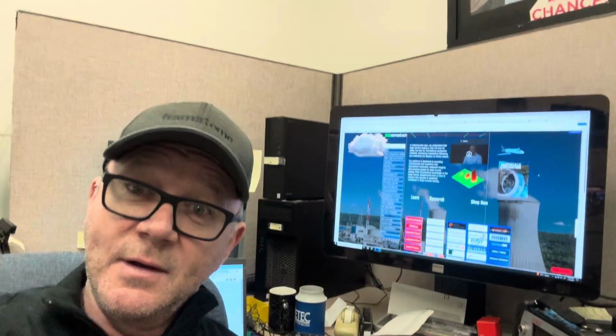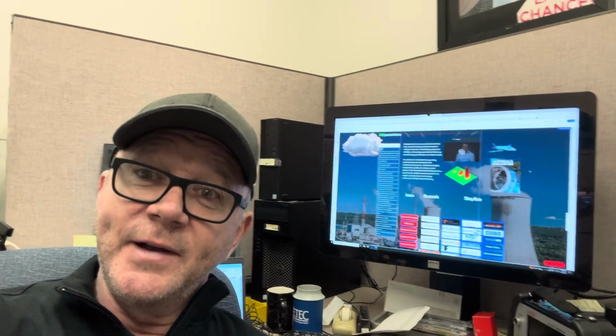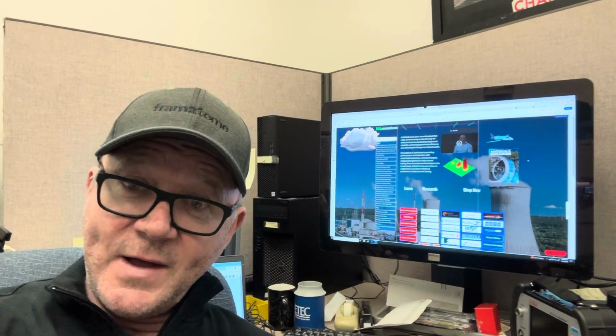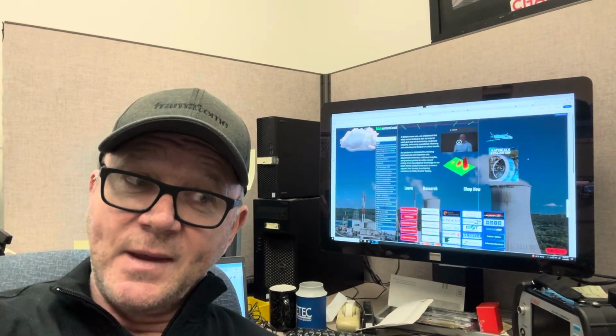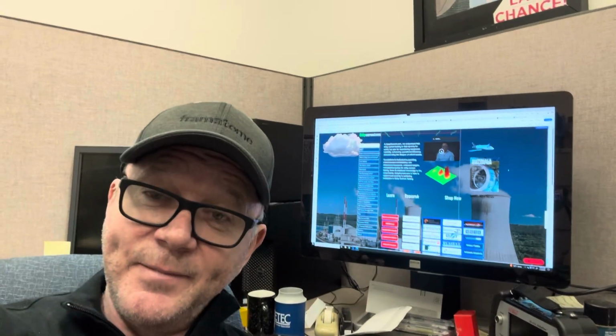Now, there's only a number of people in the whole world qualified to analyze steam generator tube inspection data, and that number seems to be getting smaller over the past few years as the Eddy Current professionals have been retiring. That creates a problem, because you still have to inspect all the tubes from all the different power plants, but when you don't have the people to do it, you're in trouble.